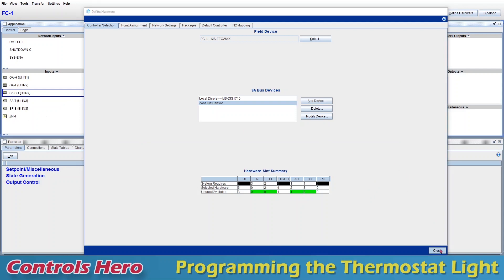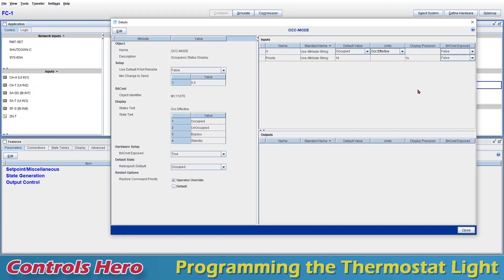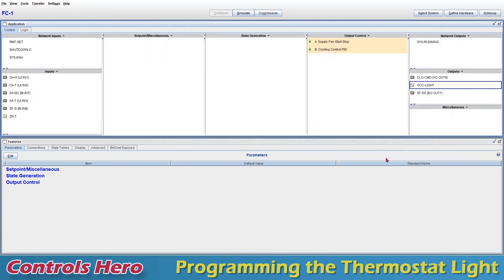It's here and you can tell I already added a point here. If I close, we also got an OCC mode. Let's double click on it. A key thing you want to look for is the point units, which you can see right here. It's OCC effective, it's a multi-value point. It has these four values: occupied, unoccupied, bypass, and standby. This is what you want to remember, occupancy effective. If you want, you can change the name of the point to make it easier to identify. Let's say OCC light, apply and I'm going to close.